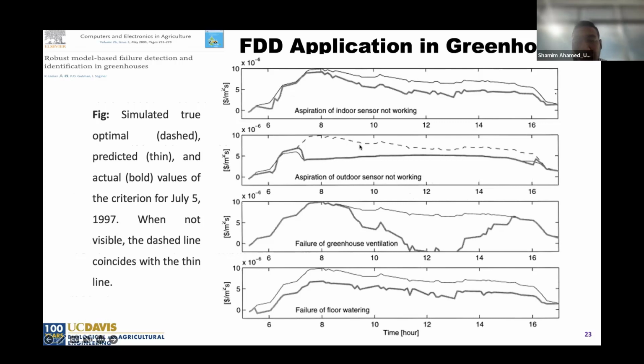This graph shows, based on that algorithm, when a fault happens. Initially the algorithm's result isn't exactly what's expected compared to the sensor data, but after a certain point you can see anomalies between the sensor data and the algorithm's output. That gives an indication that the sensor data we're getting isn't providing actual data, even though it's still giving a control signal to the control system.